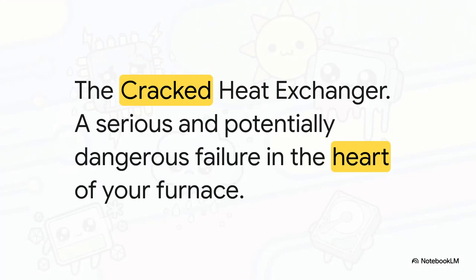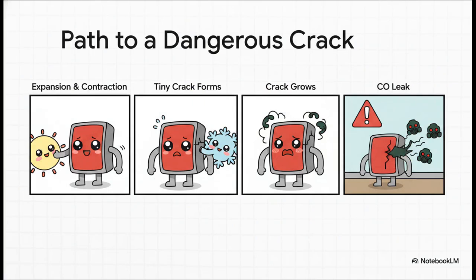The second common failure is even more serious. We're talking about the heat exchanger. This thing is basically the heart of your furnace, and thanks to that relentless thermal stress, it can develop really dangerous cracks. Day after day, that 40-degree temperature swing is flexing the metal back and forth. A tiny, microscopic fracture appears, then it grows. And this is the scary part: a cracked heat exchanger isn't just a breakdown, it's a critical safety hazard. It can leak deadly, odorless carbon monoxide gas right into your home.